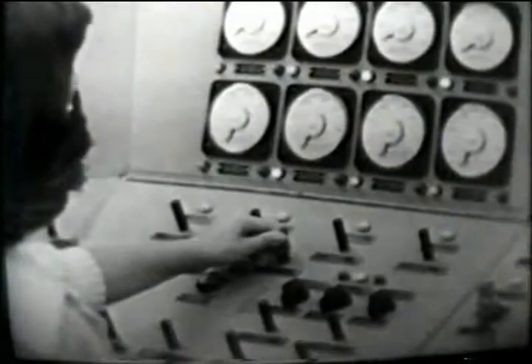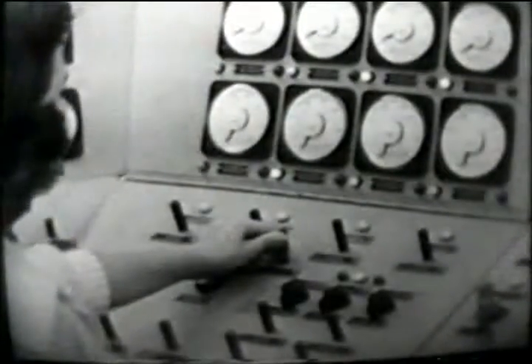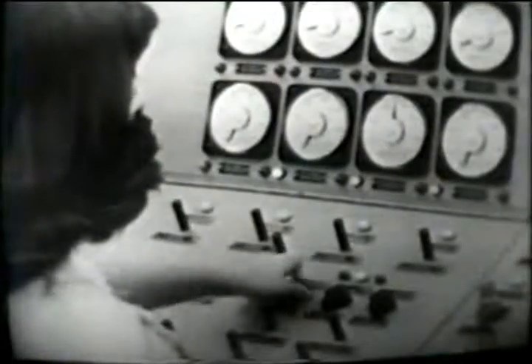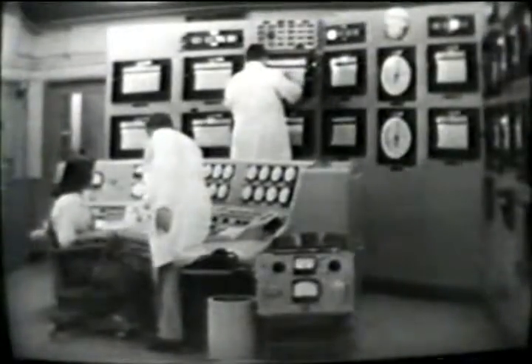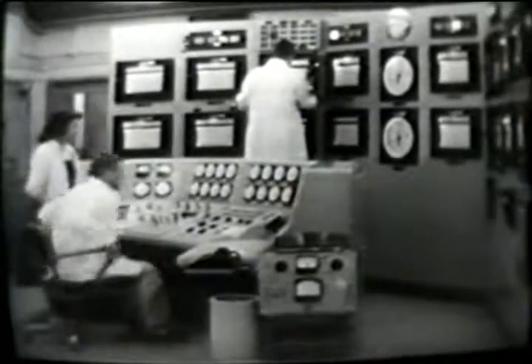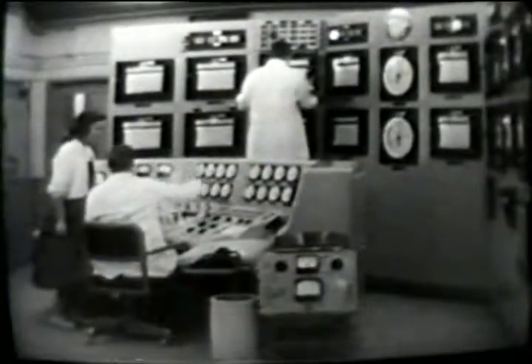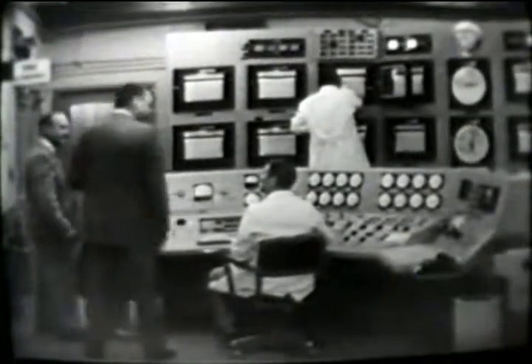These are some of the meters which indicate the positions of the control rods, which move in and out of the reactor to either stop the chain reaction or let it proceed. The buttons and levers move them up or down. The little meters indicate the exact position in inches of each rod. The meters in the back indicate temperatures, pressures, flow rates, neutron levels, and so forth. This is the nerve center of the entire reactor installation — this is where it's all controlled.